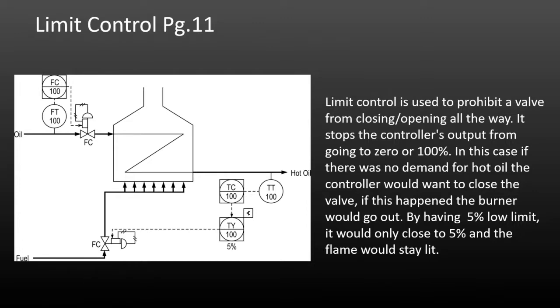In this case, if there was no demand for hot oil, the controller would want to close the fuel control valve. If this happened, the burner would go out, which is problematic because you'd have to go through a startup process. By having a 5% low limit entered into the controller, the valve would only close to 5% minimum and the flame would stay lit. That's a good example of a low limit control application.